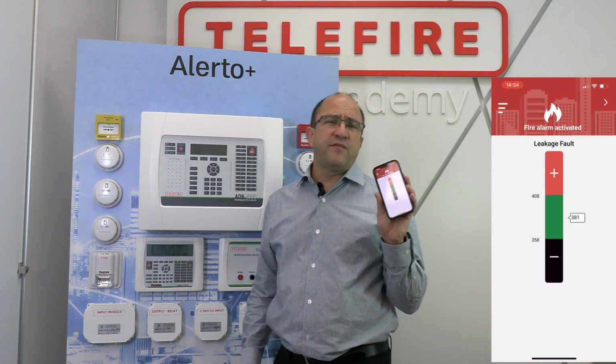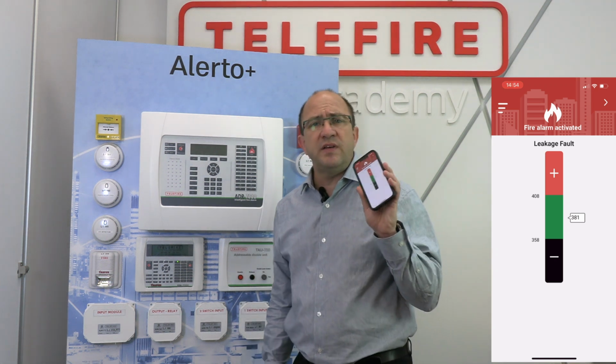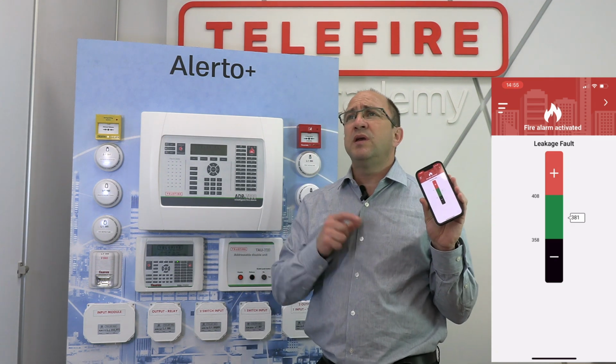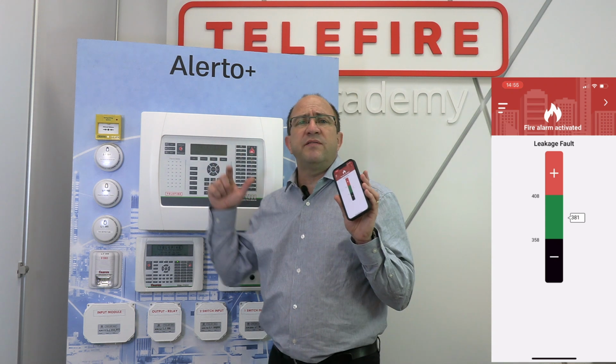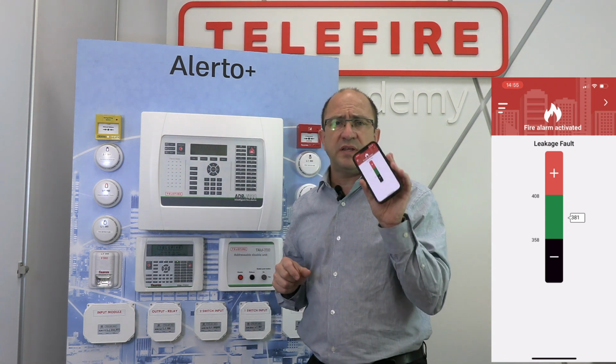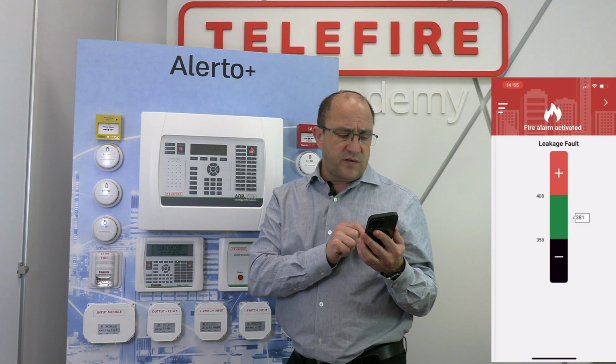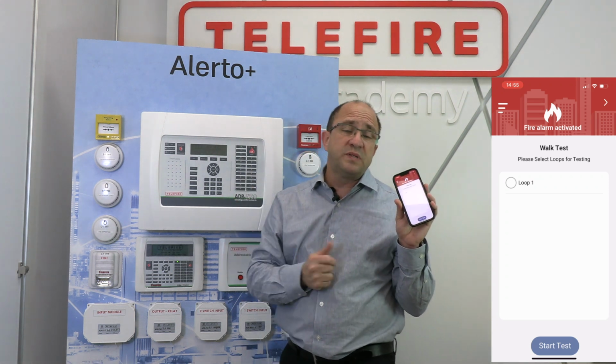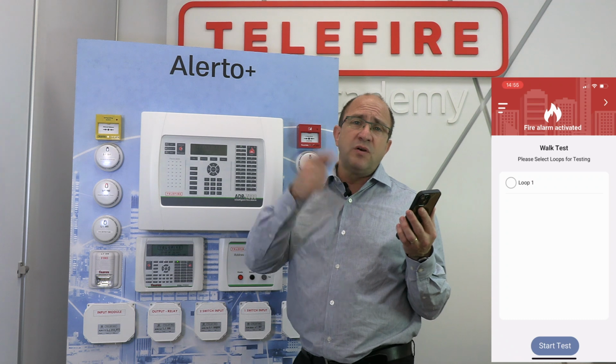I can find a ground fault on this system relatively very quickly because I have everything on my mobile and I don't need another person with me to go to the control panel, have a look to see if I solve the problem. I have it here on my cellular phone. When I go inside walk test, I can check the addresses on the loop number 1 or whatever, if I have more loops, and everything goes inside the log in the history.